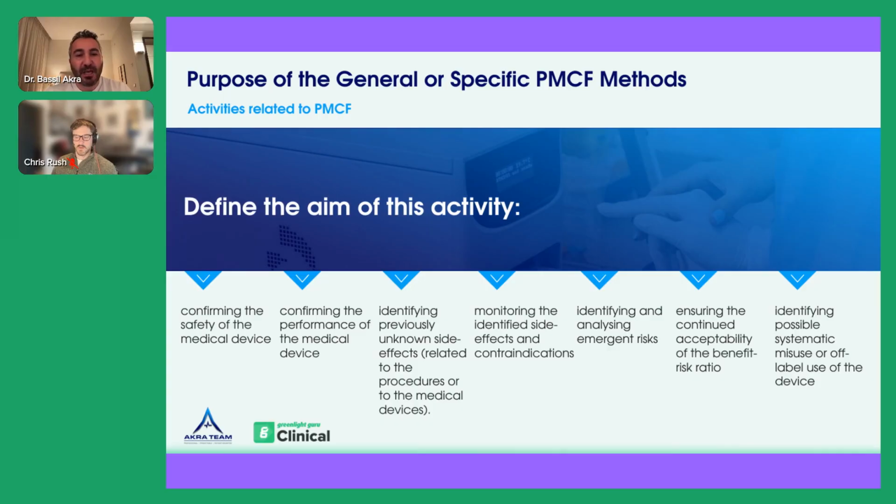So those specific PMCF doesn't need to run forever. They need to have a defined time, and that defined time comes from your expected lifetime for that device, which allows you to define how long shall I follow the patient to be able to confirm safety and performance, identify the unknown that I couldn't identify before, and so on.